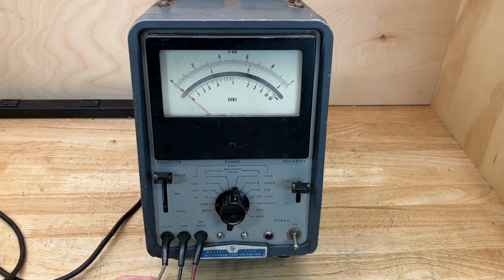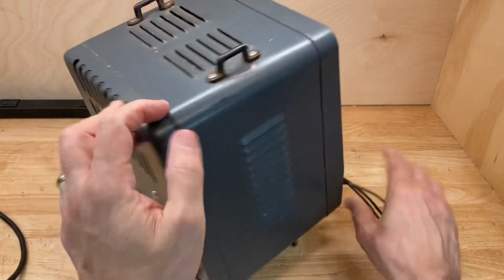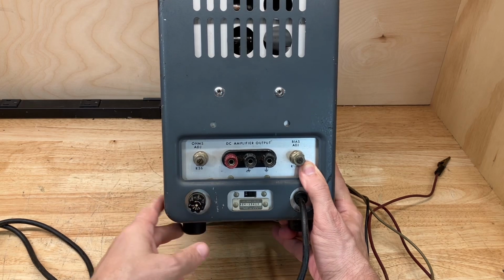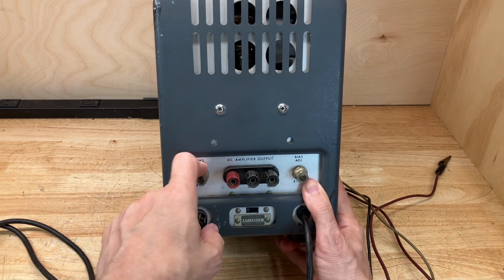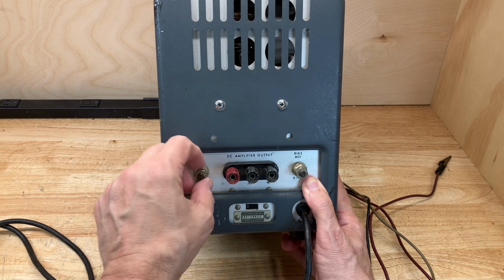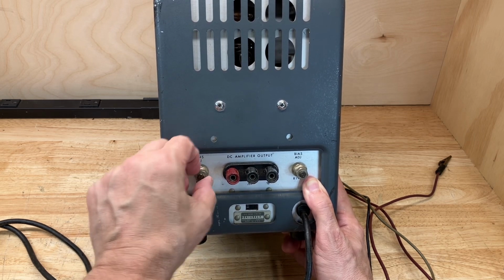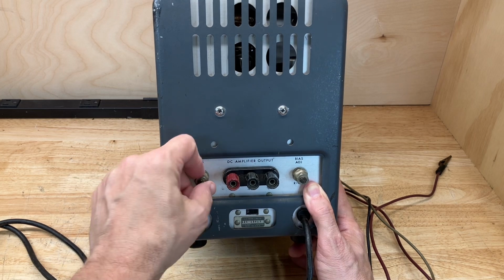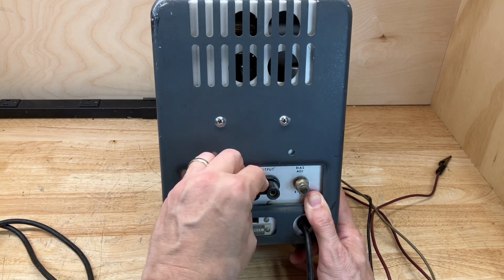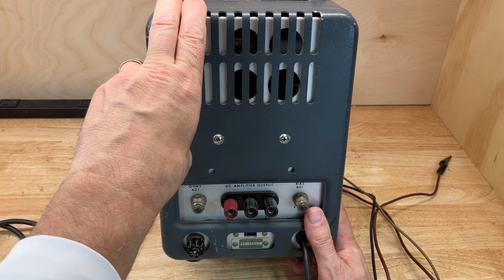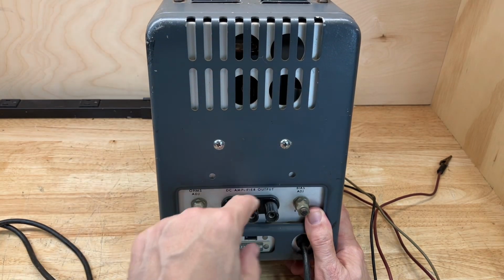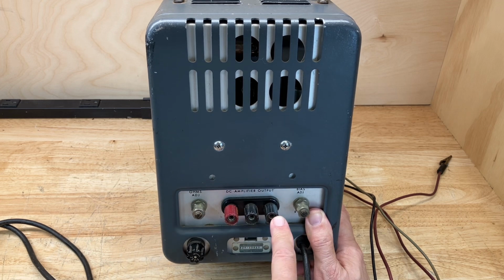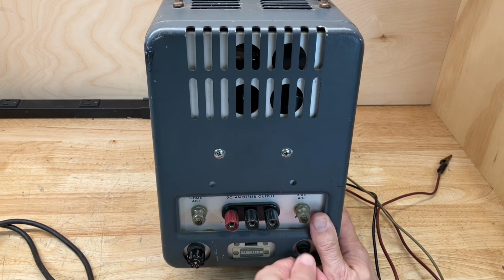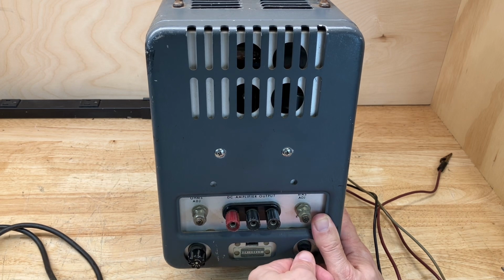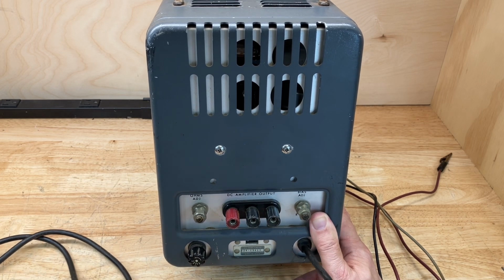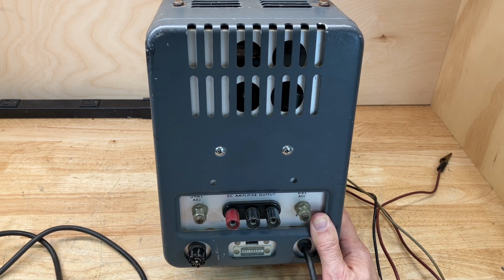So let's take a look at the rear panel. On the rear panel, we have an ohms adjustment pot and a bias adjustment pot. They are secured with a locking nut once you make those adjustments. There's a DC amplifier output. This instrument can also be used as a DC amplifier. So that output is here, and it is also floating unless you connect the load to the ground terminal. Power input. Power cable is permanently wired into the back of the instrument. Power cable is not in very good shape. I may end up replacing that as well.